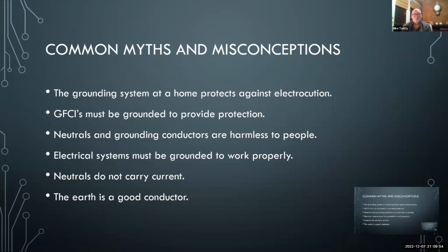Okay, neutrals and grounding conductors are harmless to people. Very untrue. Neutrals carry current by design. If you've got a 120 volt, 20 amp circuit and it's got a 10 amp load on it, 10 amps is going to be on that hot conductor and 10 amps is going to be on that neutral conductor coming back. It's going to be equal. If they're not equal, then you've got a problem. That's where GFCIs come in. That's what it's looking at, equal current on the hot and the neutral. And if that gets unbalanced by more than 5 milliamps, it trips the GFCI. So I've actually seen, unfortunately, an electrical presentation for home inspectors where the instructor repeated three different times, neutrals are not current carrying conductors. Nothing further from the truth.